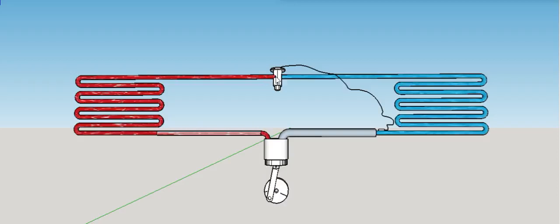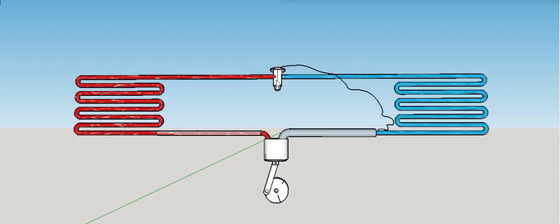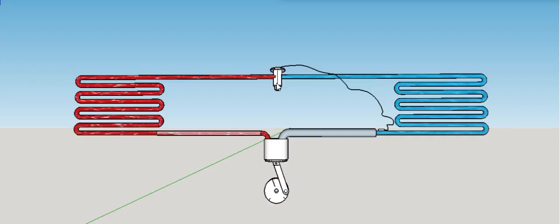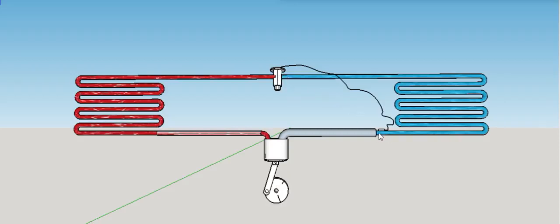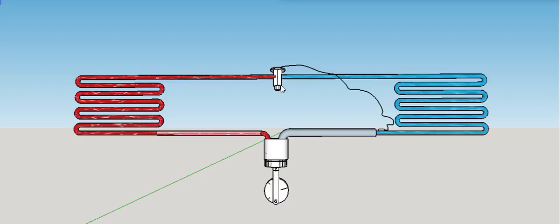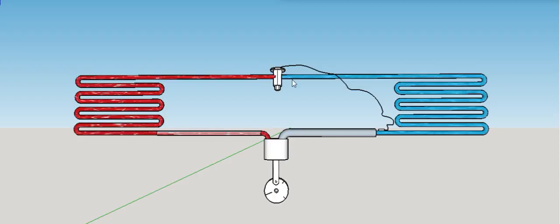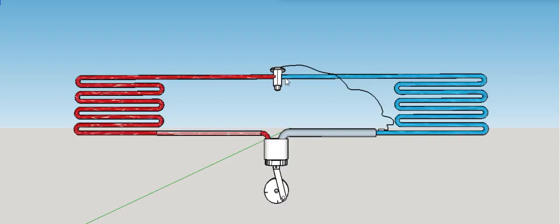The TXV is the expansion side. The TXV is basically a valve that regulates the amount of liquid flowing into the evaporator based on the temperature at the end of the evaporator. It controls how much the valve opens or closes. So a smaller amount of refrigerant, liquid refrigerant, goes to the evaporator.